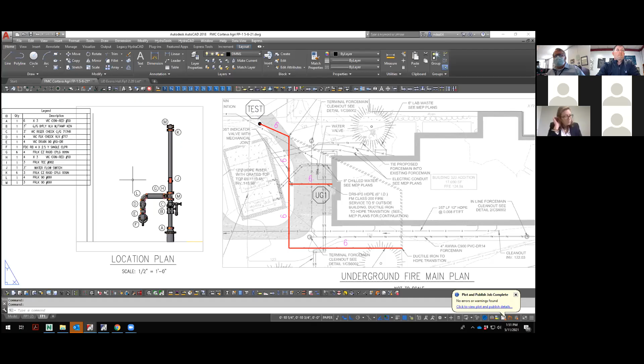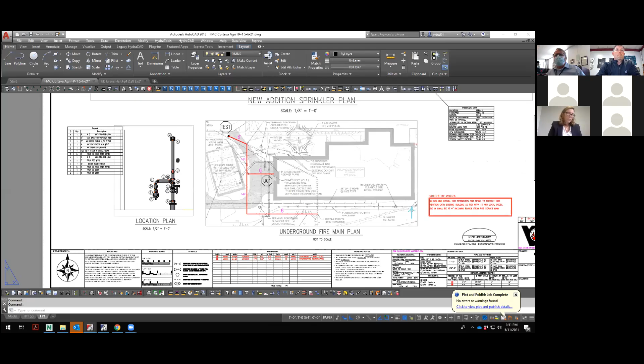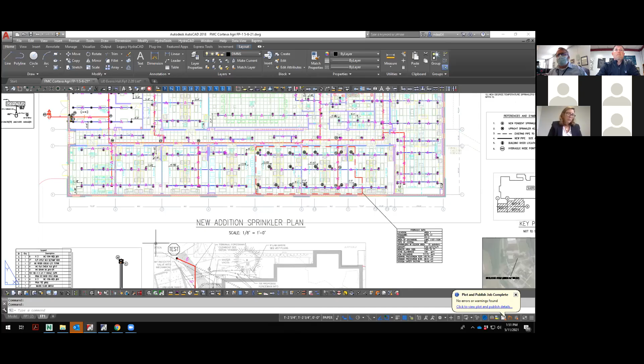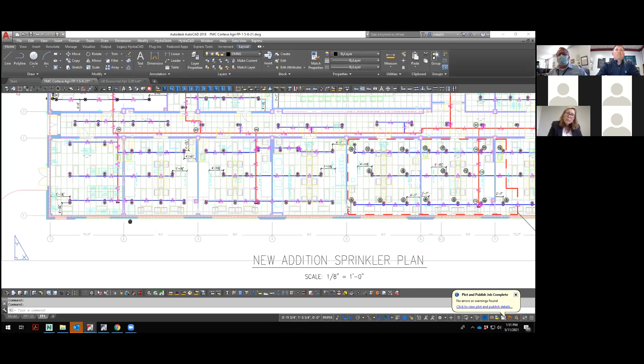And then of course it goes up to a couple of gauges for pressure, and then it goes out to an actual fire department connection, which is where the fire truck pulls up to further help supply the system. The big pumper truck will actually connect the hose to this and pump water into the system to give the sprinkler system a little bit of an extra boost if the fire is still burning. So that's actually representing what's going on here. So that's my main building riser.